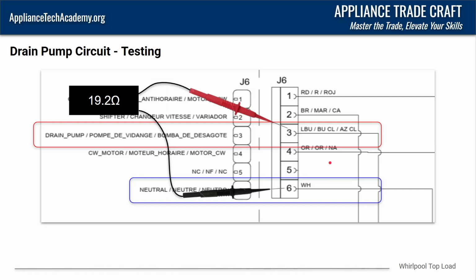So in a perfectly good circuit, if we have the J6 connector disconnected from the control board, and we get a resistance reading across the light blue wire and the white wire, we should have about 20 ohms, plus or minus. Anywhere that's close to that, you should be good. Where you're going to have an issue is if you see open line. If you're checking across those two and you have open line, that means either your drain pump is bad or your wiring is bad. If you get an open line, that's when you're going to need to tilt the unit back and check across the drain pump.